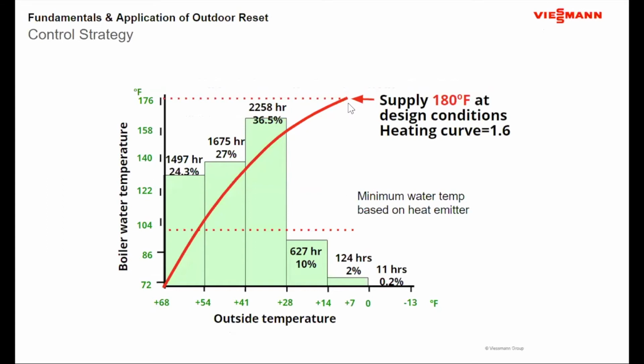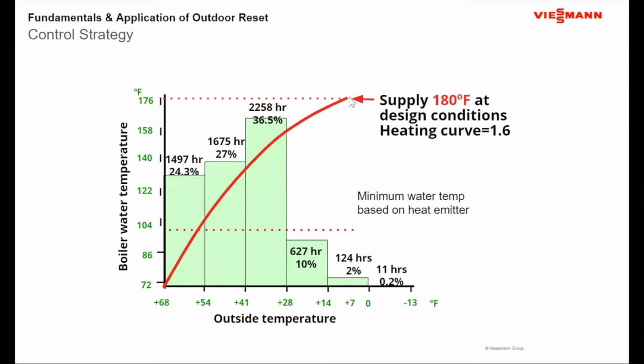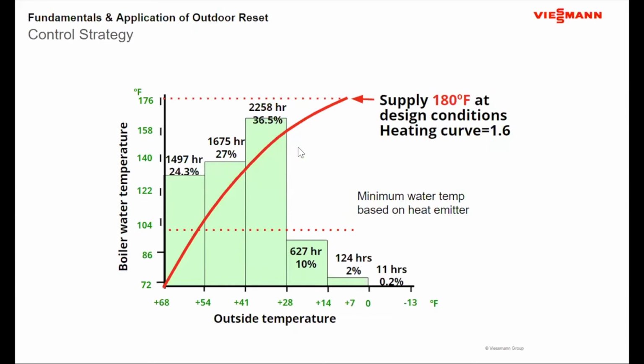And again, from an aspect of design, over here, we had the right water temperature for a very short period of time. But when I start to look at modulating the water temperature, it's not just the right water temperature for about 2% of the heating season. This is the right temperature for about 10% of the heating season, so forth and so on. And I can give myself the best match throughout that heating season to put the right amount of energy into the building to maintain comfort in the building. And equally as important, as I drive that water temperature down, the efficiency of the system goes up as well. So I start to run at better efficiencies for larger pieces of time during the course of the heating season.